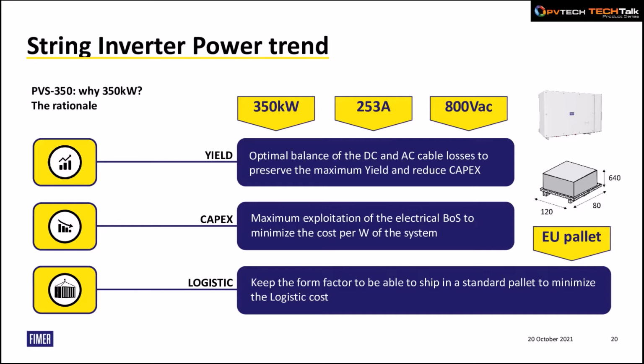Going so big in power can compromise system yields, especially because of DC and AC conduction losses. But thanks to the combination of 350 kilowatts at 800 volts AC with 253 amp output, and the ability of this inverter to receive very large aluminum cables, we're able to reach an optimal balance of DC and AC cable losses, preserving maximum yields while contributing to reduced capital cost.